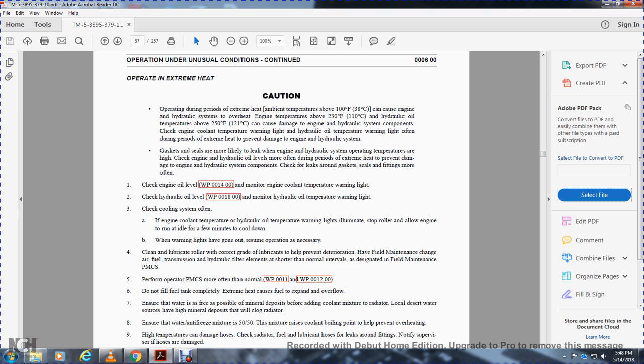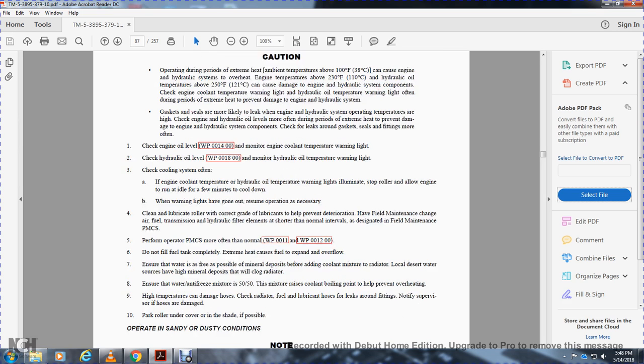Do not fill the fuel tank completely. Extreme heat causes the fuel to expand and overflow. Ensure the water is free of mineral deposits before adding coolant. Local desert water sources may have high mineral deposits that will clog the radiator. Ensure the water and antifreeze 50-50 mixture raises coolant boiling temperature and prevents overheating.